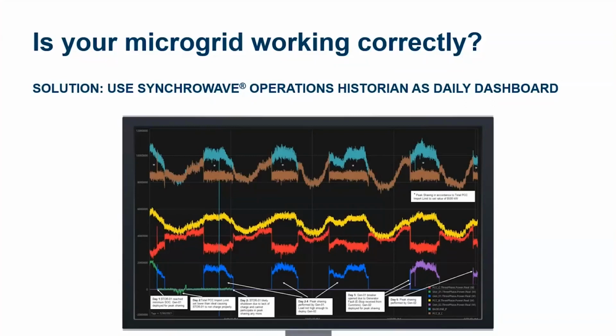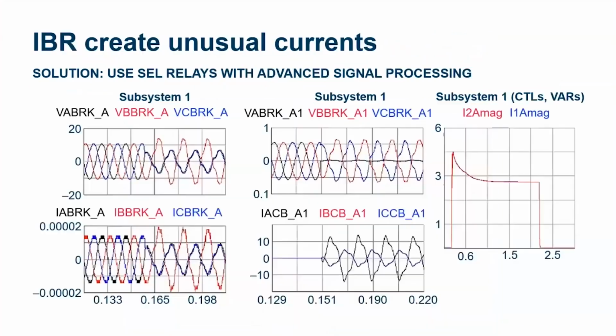Days later, the blue engine ran for 3.5 days of demand peak shaving, and the blue engine failed. It had a mechanical failure. It shut off during the attempted startup that was requested, and the SEL microgrid controller properly adapted and started a second engine to replace it. This is N-3 failure. This is resiliency. This is simplicity. And this is how you know your microgrid is working correctly.